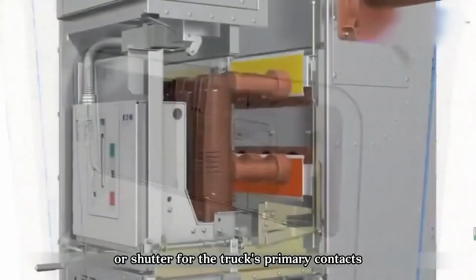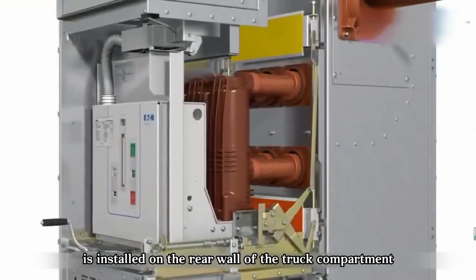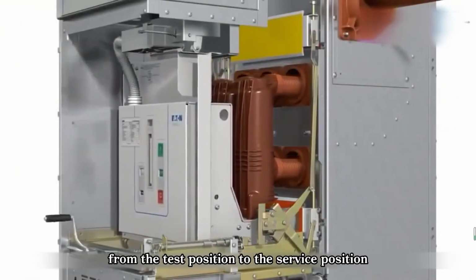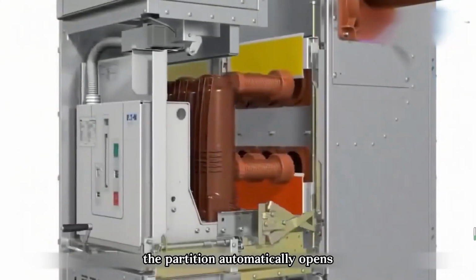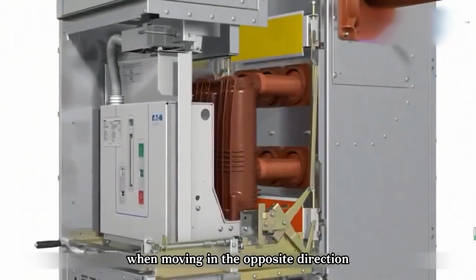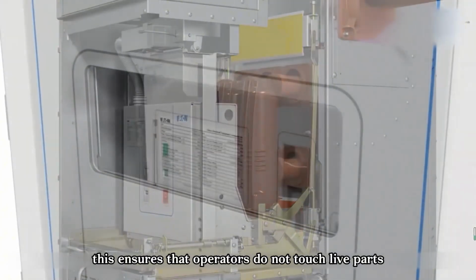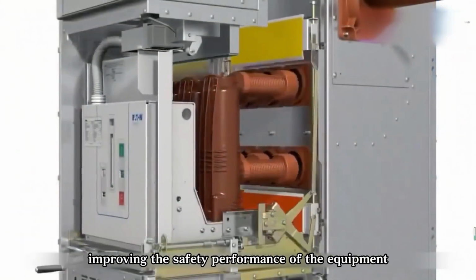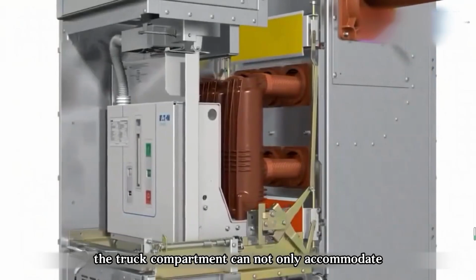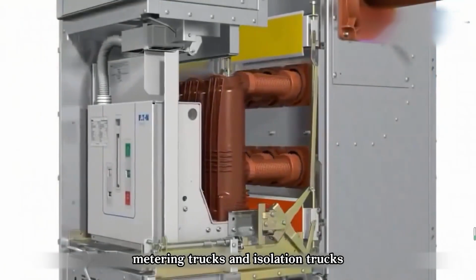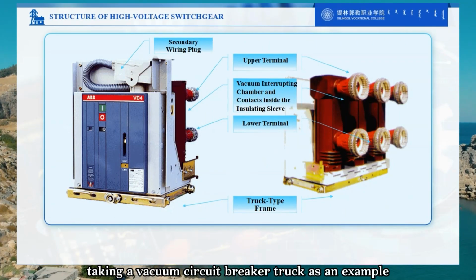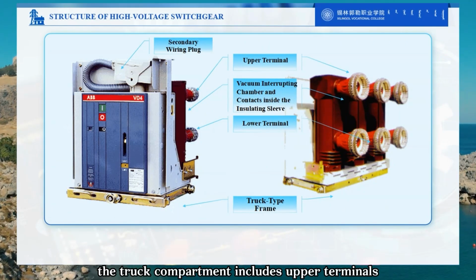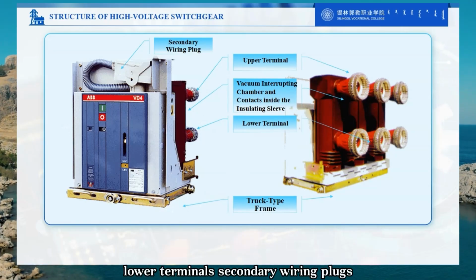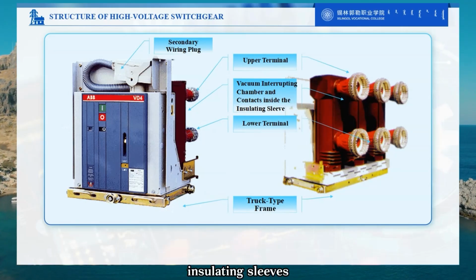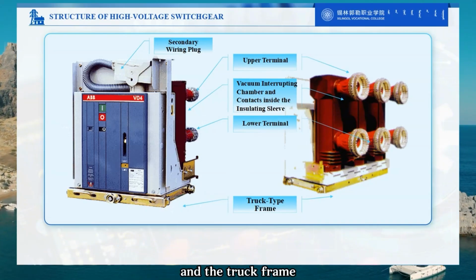The partition or shutter for the truck's primary contacts is installed on the rear wall of the truck compartment. When the truck moves from the test position to the service position, the partition automatically opens. When moving in the opposite direction, it closes completely. This ensures that operators do not touch live parts, improving the safety performance of the equipment. The truck compartment can not only accommodate circuit breakers but also PT trucks, metering trucks, and isolation trucks. Below, taking a vacuum circuit breaker truck as an example, the truck compartment includes upper terminals, lower terminals, secondary wiring plugs, insulating sleeves, with vacuum interrupter contacts inside, and the truck frame.